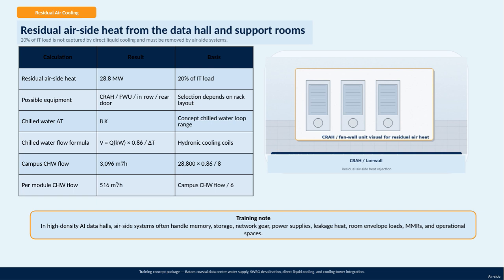Regarding chilled water flow, we use a delta T of 8 Kelvin within the chilled water loop. The calculation for chilled water flow volume is based on the heat load and temperature difference, following the formula V equals Q times 0.86 divided by delta T for this campus setup. That results in approximately 3,096 cubic meters per hour split across 6 modules, each handling around 516 cubic meters per hour. Overall, this integrated approach leverages seawater reverse osmosis desalination, direct liquid cooling, and cooling tower systems, ensuring efficient management of residual heat through carefully designed airside cooling components.